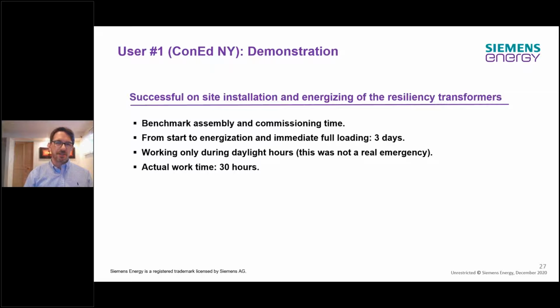But what was the result of the demonstration? Con Ed was extremely satisfied with what they were able to achieve, definitely benchmark assembly and commissioning times. From the start of the process, which included bringing the resiliency units from the warehouse to the substation, to installation of the bushings, installation of the cables, wiring of the protection and control cables, to full loading, energization, and immediate full loading of the transformers, less than 3 days. So this is really benchmark. And as we said before, normally this process takes 4 weeks.